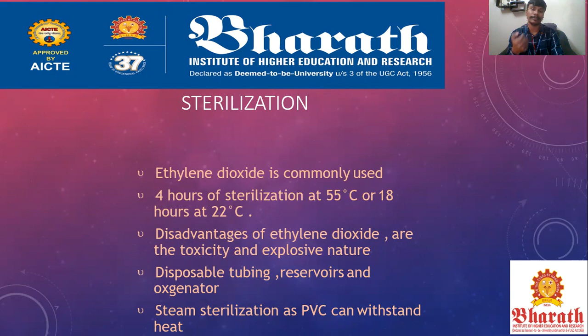The things to be reused for another patient will be sterilized for 4 hours at 55 degrees Celsius for quick usage. If it is not for quick usage, it will be 18 hours at 22 degrees Celsius. It can also undergo steam sterilization, as PVC, polyvinyl chloride, can withstand the heat. This property is also why PVC is used for tubing in the heart-lung machine.